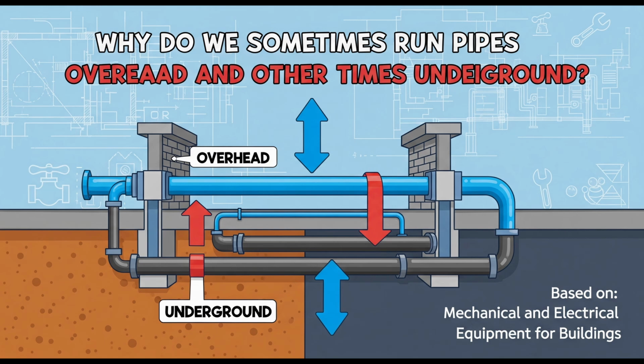Say to the top floor of a really tall skyscraper, like 60 floors up. Street pressure won't cut it, surely. Absolutely not. No way. This is where pressure management becomes a huge, complex engineering challenge. In very tall buildings, you just can't use a single pressure system fed directly from the street main. The pressure needed to get water to the top floors would be enormous at the bottom, like dangerously high. It would burst pipes, blow out faucet washers. Okay, yeah, that sounds bad. And conversely, the top floors wouldn't get enough pressure, maybe just a trickle.